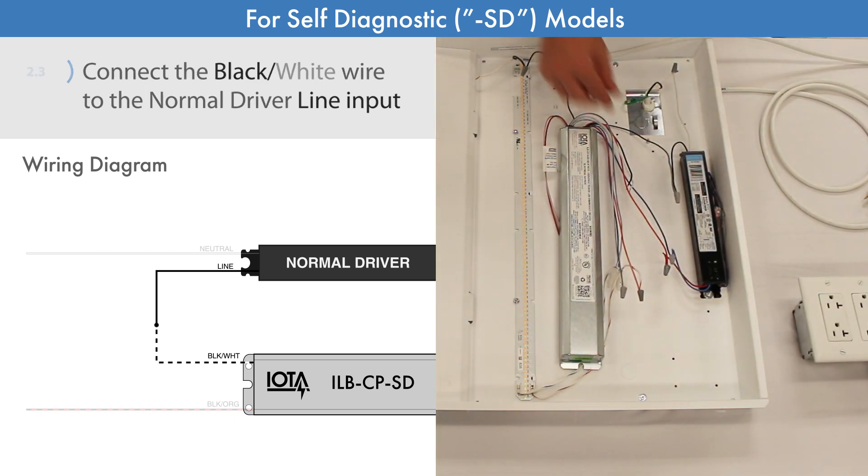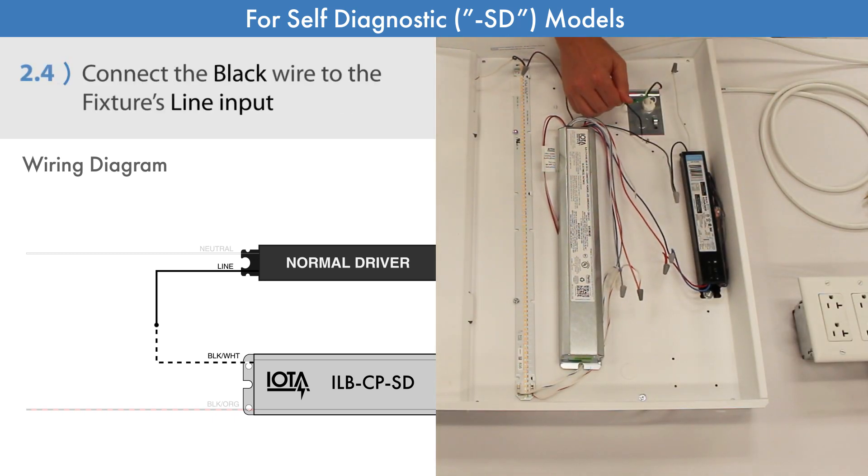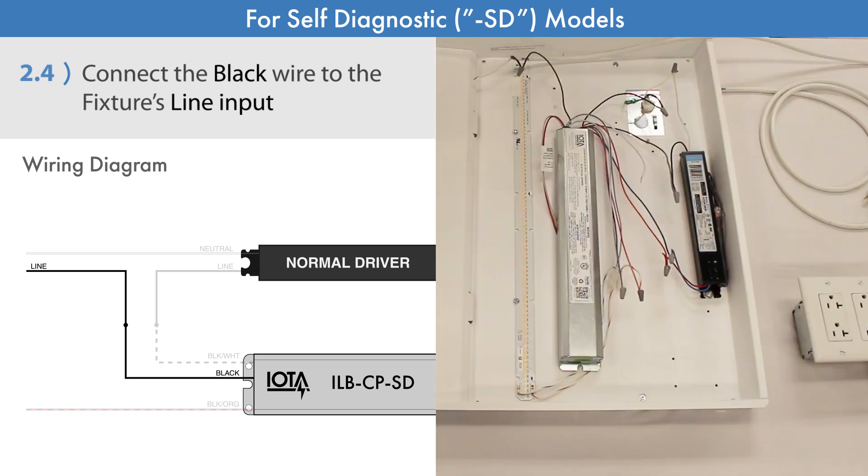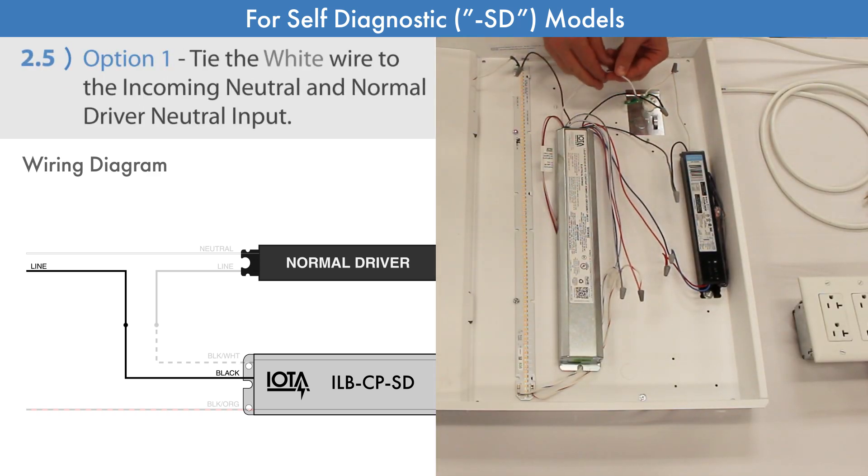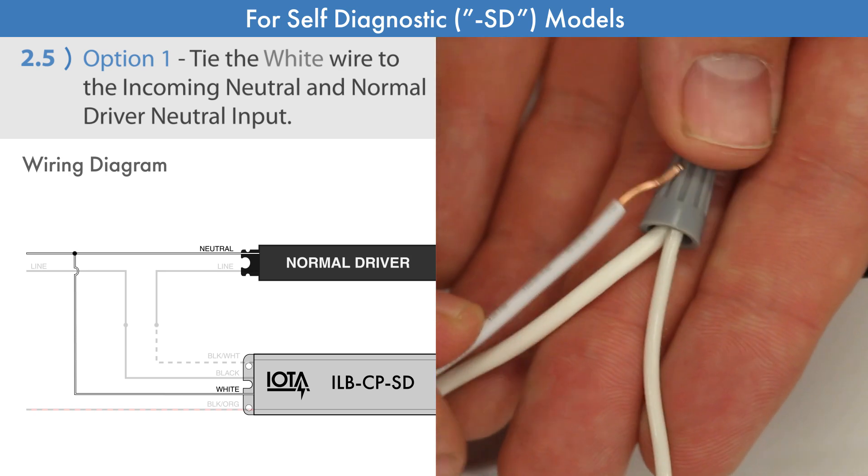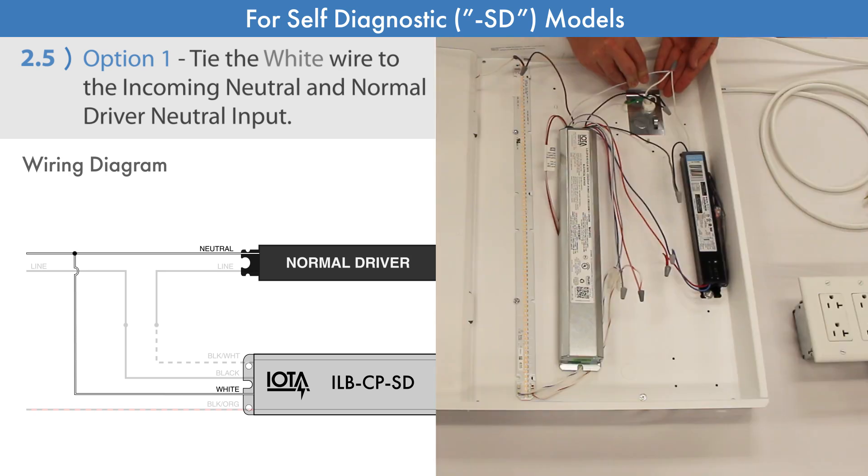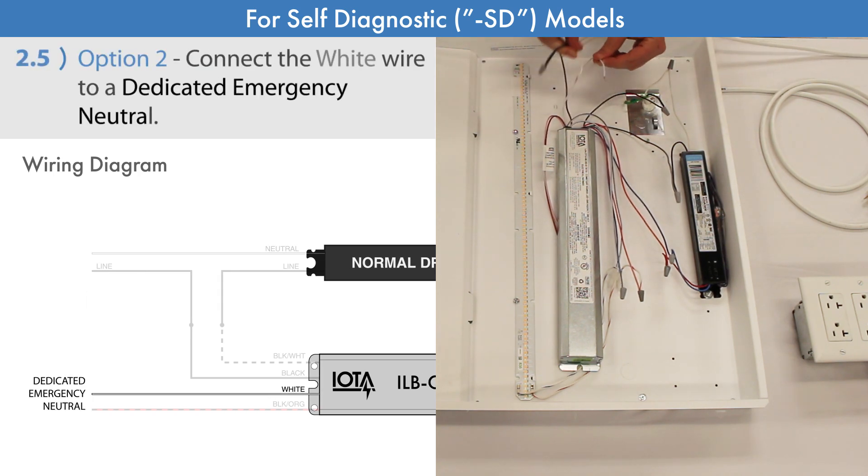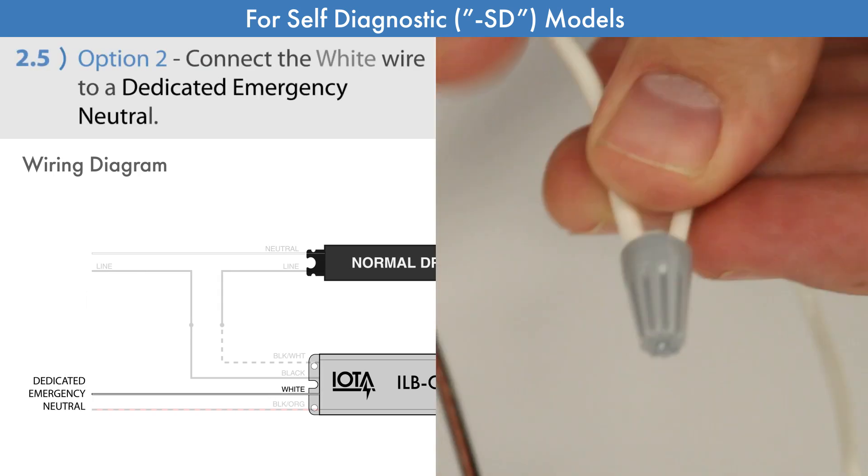The next step is to connect the black wire from the ILB-CP to the fixture's line input. And lastly, you may either tie the white wire together with the fixture's incoming neutral and the normal driver's neutral input, or if you have a dedicated emergency panel, you may connect the white wire to its neutral output.